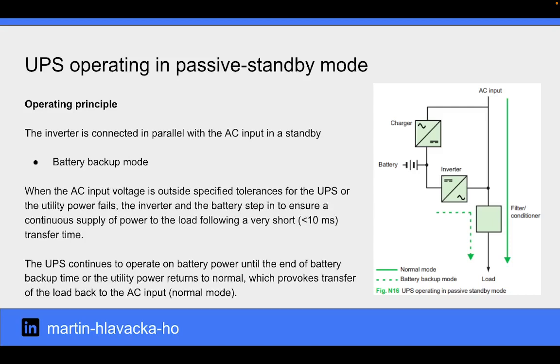In battery backup mode, when the AC input voltage is outside specified tolerances for the UPS or the utility power fails, the inverter and the battery step in to ensure a continuous supply of power to the load following a very short transfer time. The UPS continues to operate on battery power until the end of battery backup time or the utility power returns to normal, which provokes the transfer of the load back to the AC input.